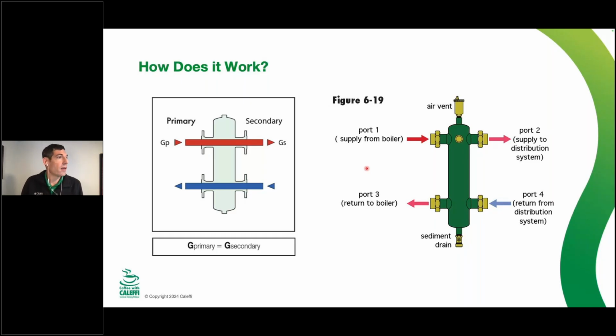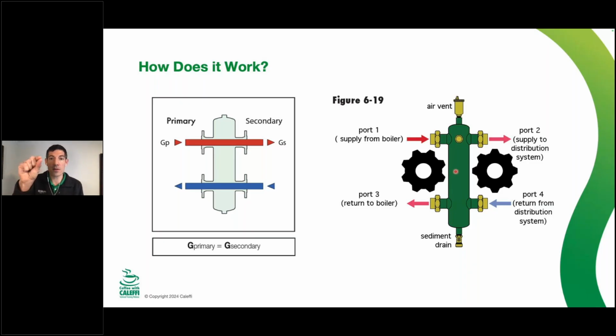Let's say, for argument's sake, that we have a hydro separator, and on one side from the boiler here, we have a circulator running at exactly 10 GPM. And going out to the system, very improbable, but let's say the system side is exactly 10 GPM as well. Both of these wheels are spinning at exactly the same speed. So if you put a drop of blue food coloring right in the center of this hydro separator, and you 3D printed this entire thing out of a clear polymer or something like that, that food coloring is just going to kind of float right in the middle. There's no cross from the top to the bottom here. It's just going straight from the left to the right and from the right to the left on the way back. So we don't really have much interaction in the center of the vessel.